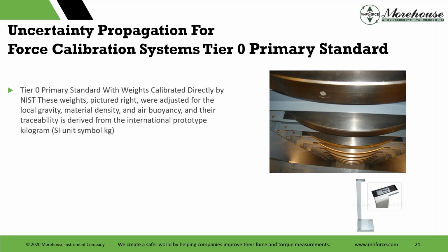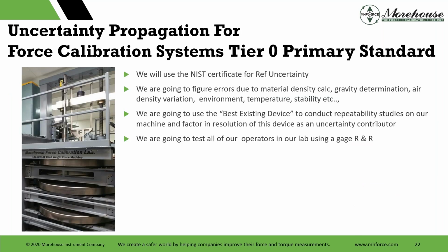No, NIST derives their traceability, and that's how we get it. We adjust our weights. We have local gravity done on site. We have coupons of the material at different levels for our machines, where somebody like Troemner or Rice Lake will do a density analysis of those to give us the actual material density. And then we monitor our air buoyancy, and we have a device for that. It's like 0.001. I forget it off the top of my head, but yeah, we have a Vaisala device that we've been monitoring for a year's worth of data and buoyancy and calculate it out that way.